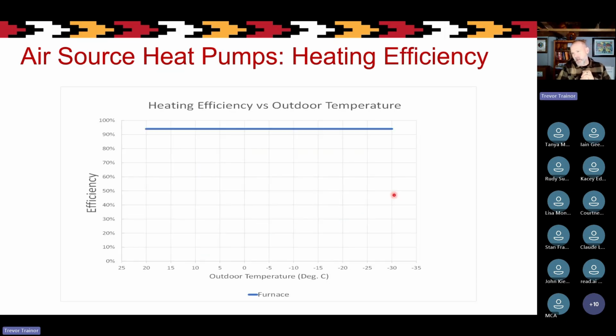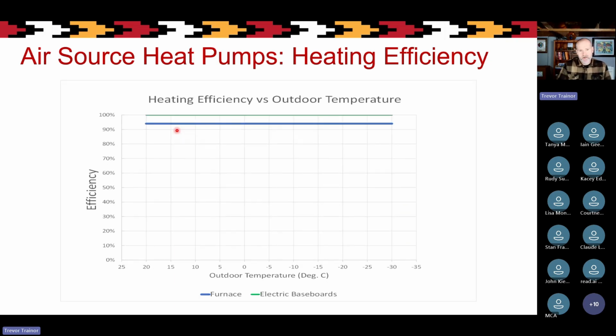And so the other thing that changes as the outdoor temperature gets colder is the efficiency of the air source heat pump. So again, a furnace, if it's natural gas or propane or oil, it doesn't matter what the outdoor temperature is really. It always operates at, let's say, in this case, 94% efficiency, okay? Electric baseboards, on the other hand, will run, no matter what the outdoor temperature is, at about 100% efficiency. You think, well, how can you do better than 100% efficiency? Well, actually, heat pumps are really good at that.